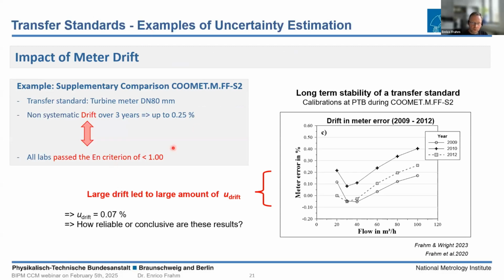So in this case, a turbine meter was used, and here also a large amount of meter drift over the 3 years was detected, but this detection was not systematic. So the turbine meter showed a large meter drift over 3 years, which was followed by a large amount of meter uncertainty here. So nevertheless, all labs passed the EN criterion. So on one hand side, a large meter uncertainty was detected, and on the other hand side, all labs passed the standard EN criterion. What does that mean?